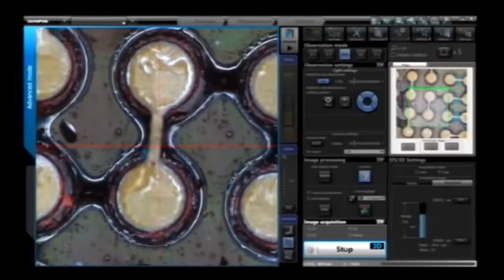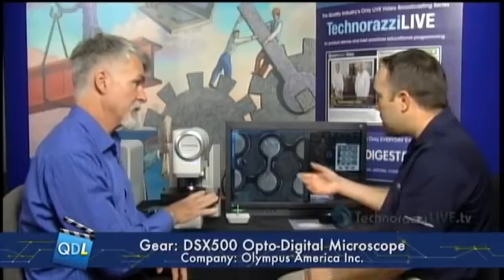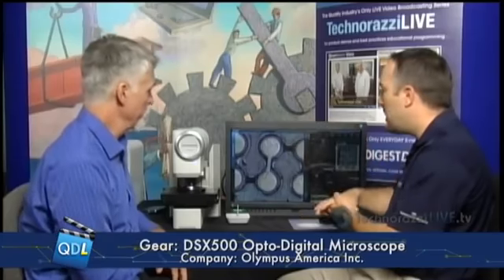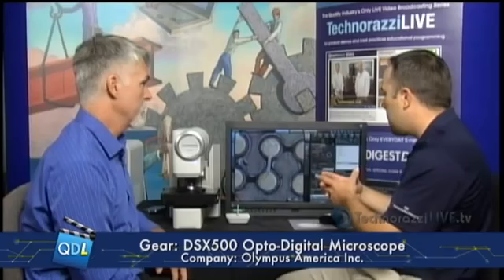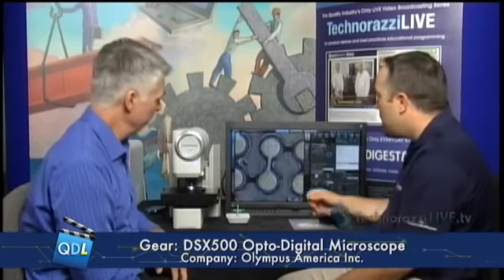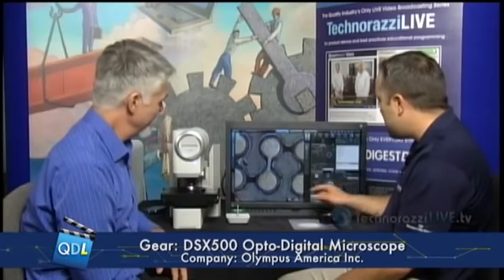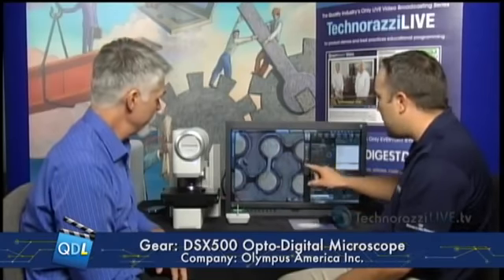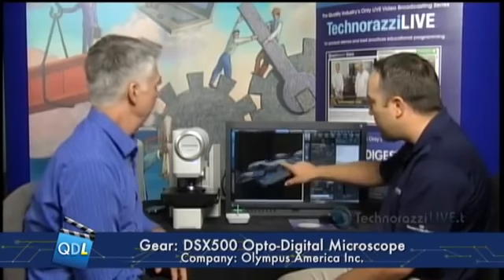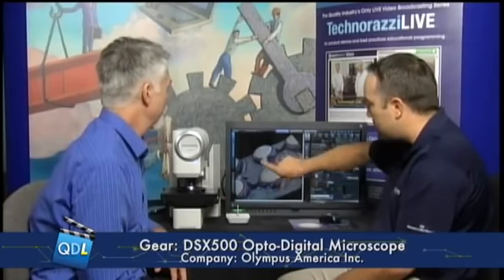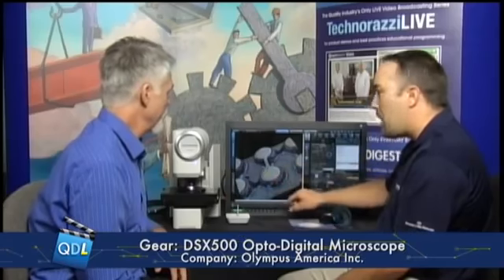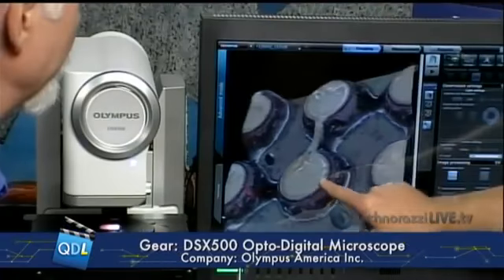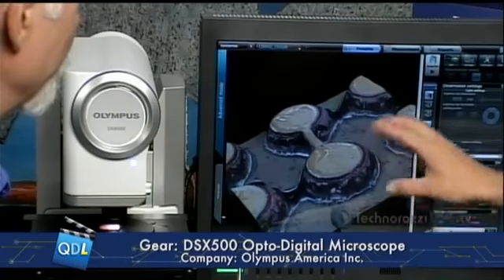Okay, so it's stepping and then focusing, stepping then focusing. It's actually stepping from bottom of focus to top and capturing all the focus slices between there, and integrating it into one focused image using an imaging technique to cut out the out-of-focus data. Okay. So when you're all done, you get an all-in-focused image. Right. And since we selected 3D here, it captured all the height information since it knows very precisely where you're going. Oh, very cool. We can render a three-dimensional image, zoom in and out with our touch screen. And you can rotate it, you can control that image just with your finger on the touch screen, or you can use your backup mouse if you'd like.